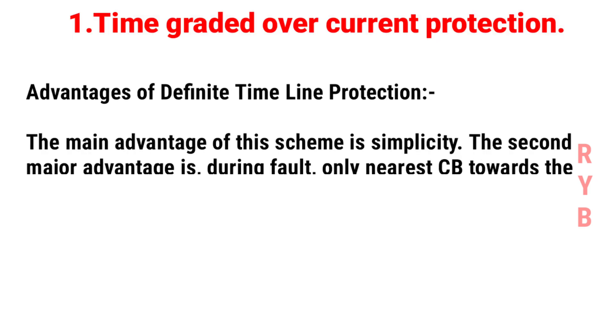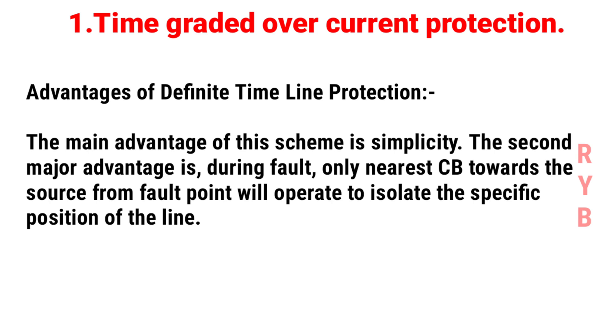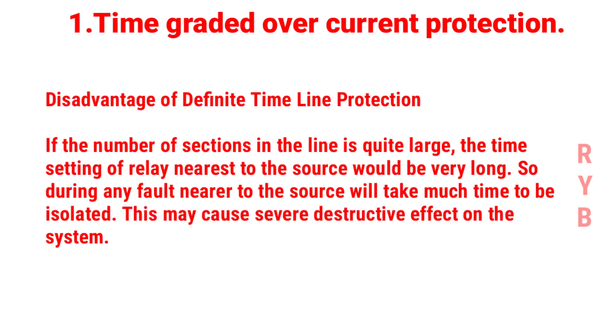The main advantage of this definite time protection scheme is its simplicity. During a fault, only the nearest circuit breaker towards the source from the fault point operates to isolate the specific section of the line. However, if the number of sections is quite large, the time setting of the relay nearest to the source would be very long, causing a fault near the source to take much more time to be isolated, which may cause severe damage to the system.